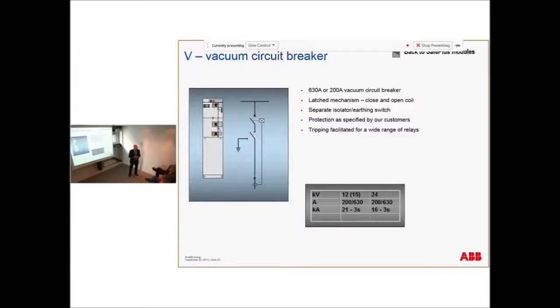Yes. The interlocking of the earthing switch. If the cable coming in is energized, is it mechanically or electrically? How is the interlocking done? All interlockings are mechanical. But you mentioned an important point.